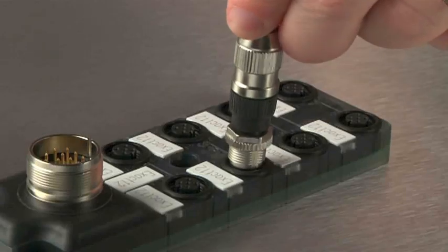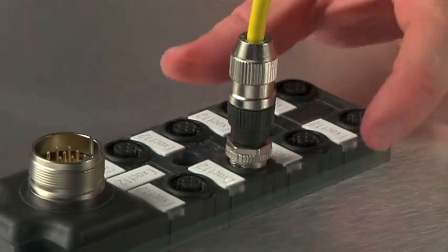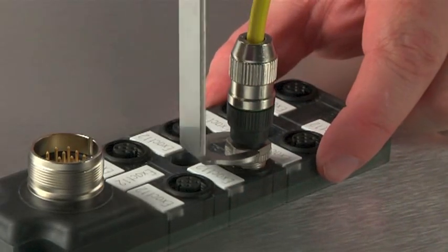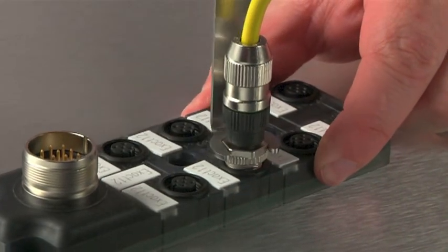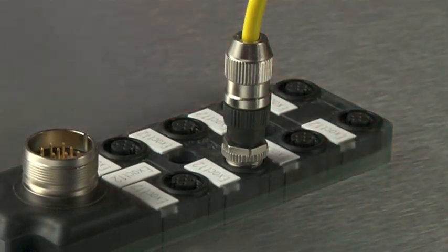Final assembly for installers with experience is usually less than 2 minutes and results in IP67 protected connections. IDC products can be reused up to 5 times. This allows for a lot of flexibility when cable appearance and protection is important.